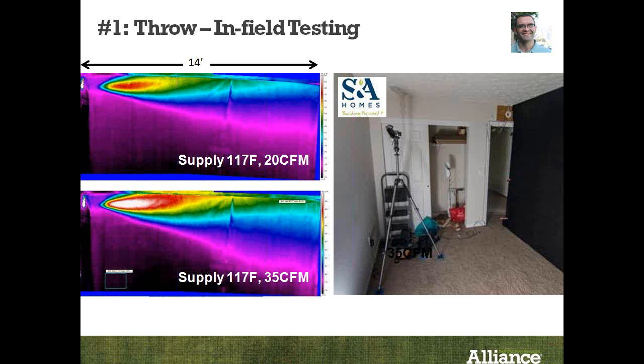We had a question from the audience, and I think it speaks directly to this issue. So the question is, with the smaller diameter and narrower throw, do you need to add more supplies to each room to ensure full room comfort? No, you basically add the number of supplies to the room to meet the load, but we have an illustration showing that in a couple more slides, but ultimately what you have is, because you have a long throw, you have more surface area of the air moving into the room, being able to mix with other air in the room. Does that sound right, Andrew? Yeah, that's exactly what happens.